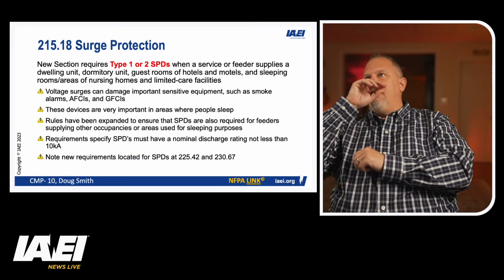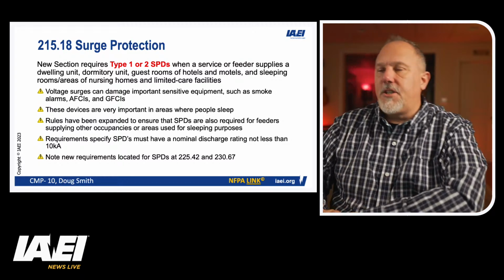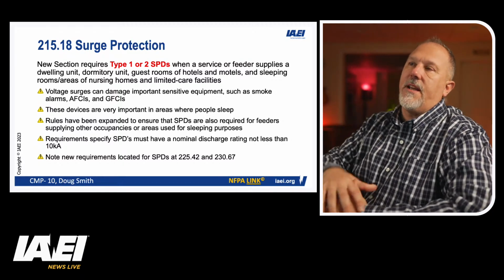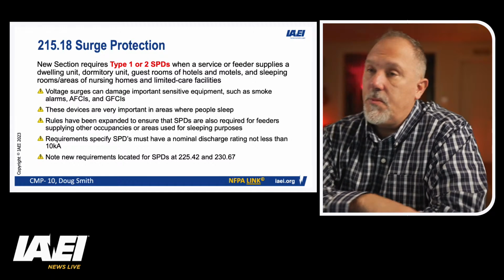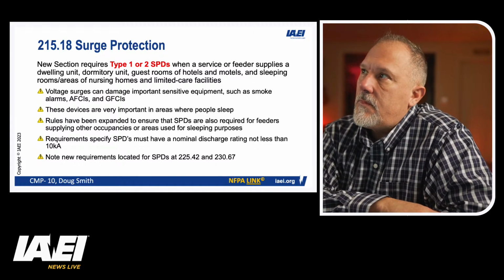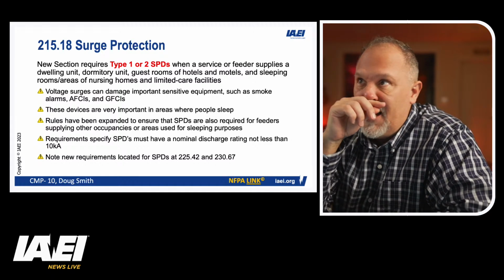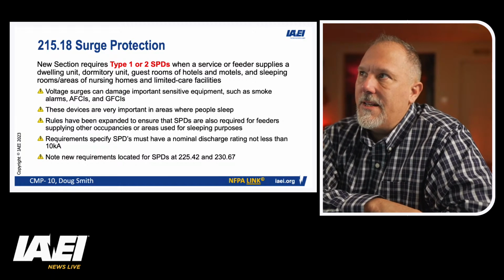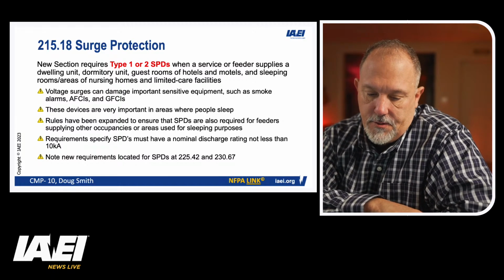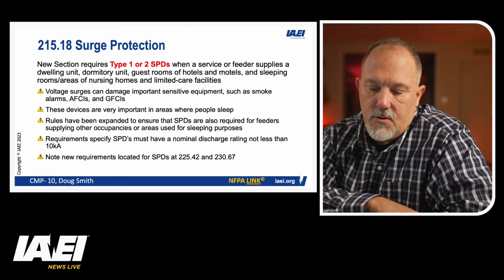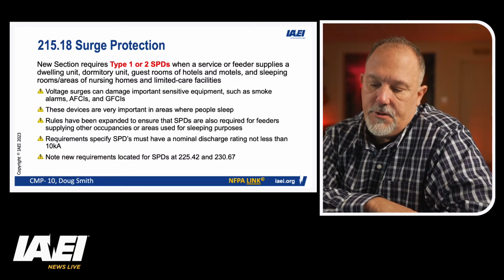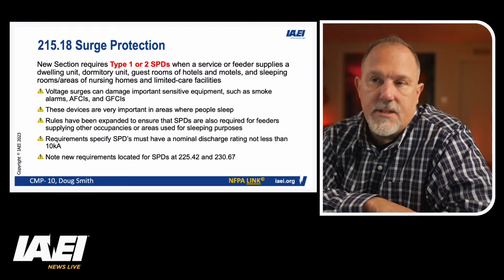Okay. So 215.18 surge protection. There's a new section that requires Type 1 or Type 2 surge protective devices when a service or feeder supplies a dwelling unit, dormitory unit, guest rooms of hotels and motels, and areas of nursing homes and limited care facilities used exclusively as patient sleeping rooms.